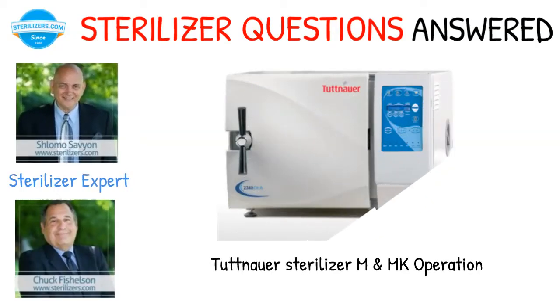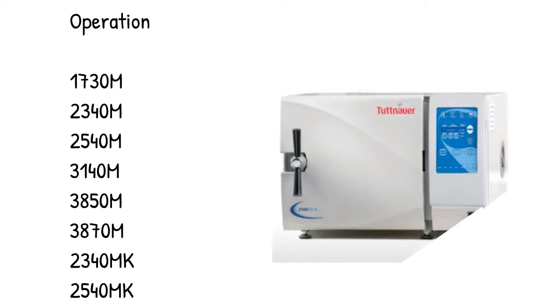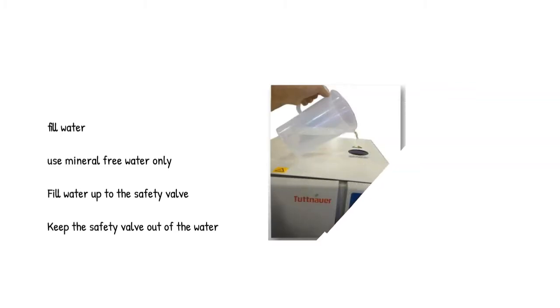Sterilizer questions answered. Tuttnauer sterilizer M and MK operation. Models 1730, M2340, M2540, M3140, M3850, M3870, MK2340, MK2540. Fill water. Use mineral-free water only. Fill water up to the safety valve. Keep the safety valve out of the water.